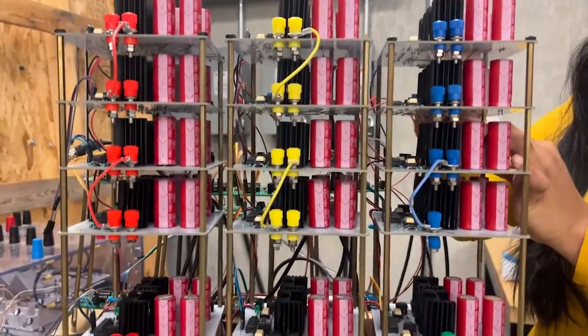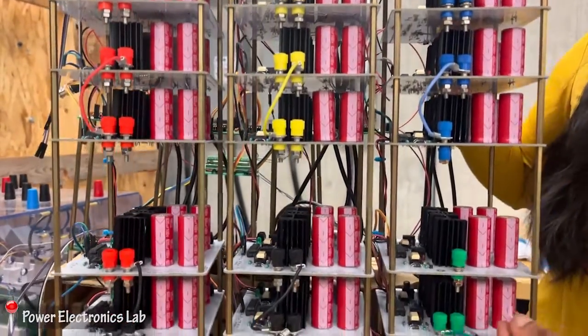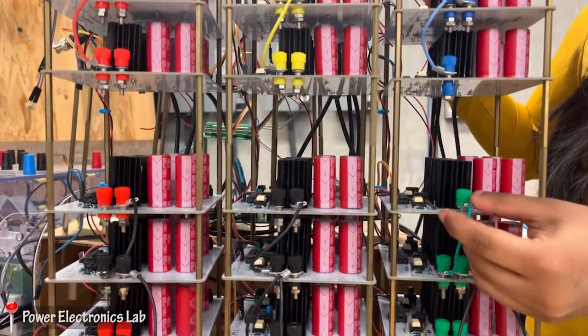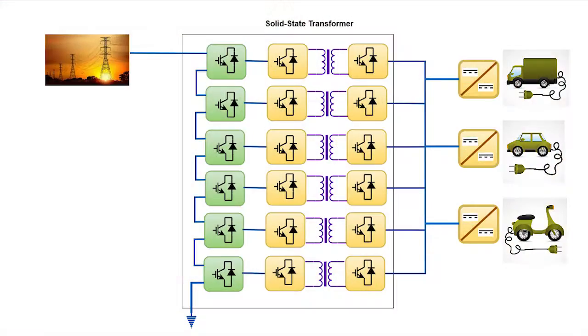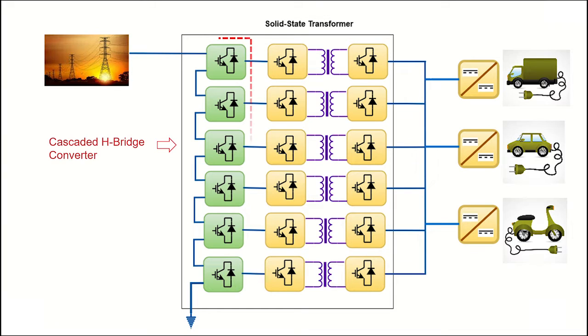High-power solid-state transformers are modular in nature to reduce the voltage stress on power electronic switches. This is the basic configuration of SST-based charging station. First, the medium voltage AC is converted to DC using a cascaded H-bridge converter.